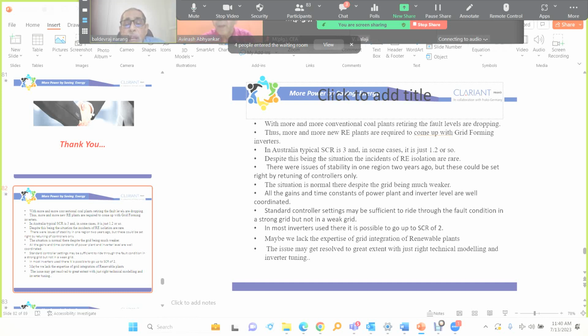If we have only a problem of voltage adjustment, if it is only to recover the voltage, definitely STATCOM or the inverters are the best devices and they can cope with that. But suppose the problem is not just voltage control or voltage stability, suppose the problem is much deeper, and the fault levels are beyond control of the inverters. Then whether we have inverter or STATCOM, the phase lock loop controllers are not able to detect the situation, or not able to correct it. They have to either trip or go into an oscillatory mode, undamped oscillations, and the situation is not safe.